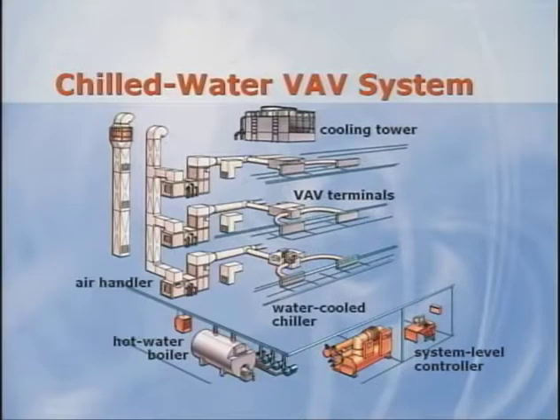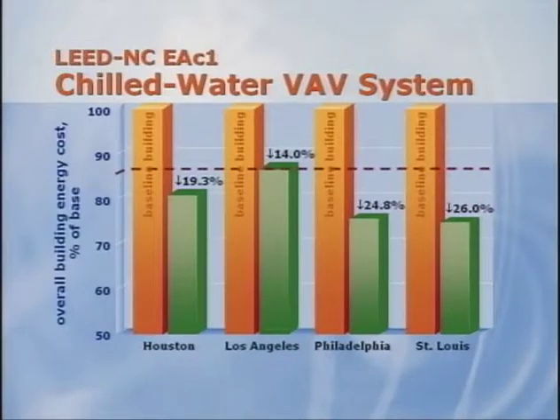Our last comparison takes the chilled water VAV system defined by Appendix G of 90.1 for this baseline building and modifies it to improve its energy performance. Chilled water and hot water are produced at a central location and pumped throughout the building to VAV air handlers. Each air handler delivers a mixture of outdoor and recirculated air to several VAV terminals which serve the individually controlled zones. Here's the chart comparing the proposed building with the high-performance chilled water VAV system to the baseline.